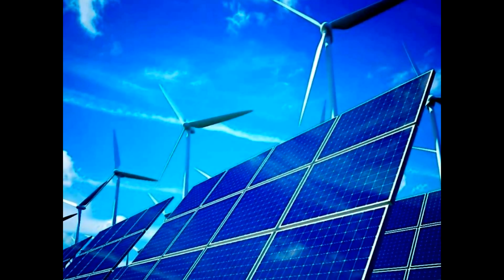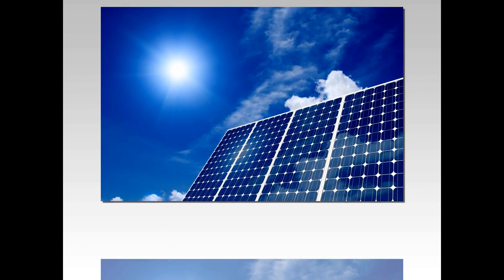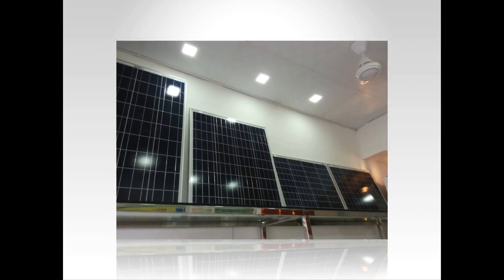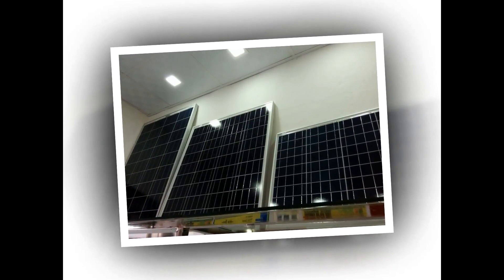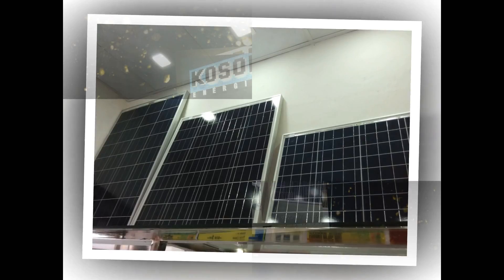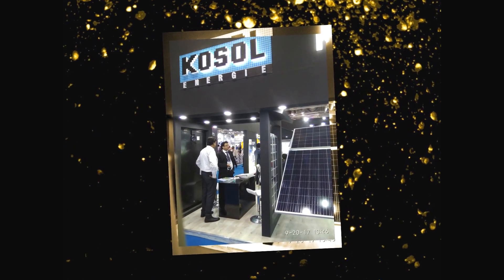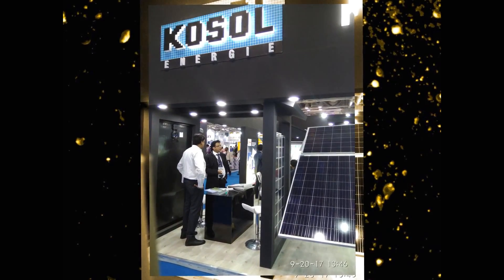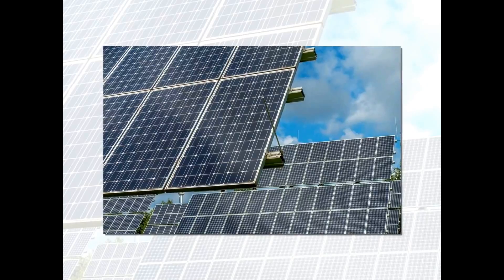Our main focus is to discuss Grid-Connected Rooftop Solar Power Plant. On-Grid Solar Systems generate power during the daytime equivalent to the sanctioned load of the consumer, which is utilized fully by powering captive loads and excess power is fed into the grid as long as grid is available. Where solar power is not sufficient due to climatic conditions or cloud cover, captive loads are served by drawing power from the grid through a bi-directional net meter. The beneficiary pays to the utility on net meter reading basis only.